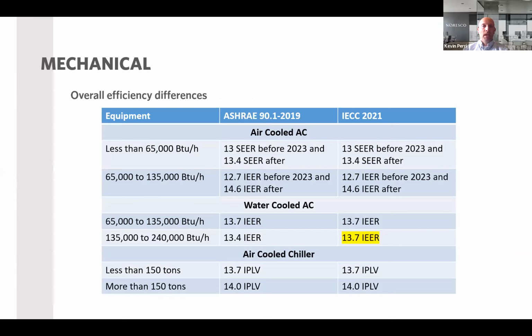There are pages and pages of equipment listings in both IECC and ASHRAE. What I did is I just grabbed 6 here just to give you a sample of what that looks like. Again, I tried to make it simple and highlight in yellow the only differences. So right now, what I'm showing you on the screen is water-cooled air conditioners between 135,000 and 240,000 BTUs have a different efficiency rating between the 2 pathways. Other than that, in the 6 that I'm showing, the efficiencies are exactly the same no matter which pathway you go down.